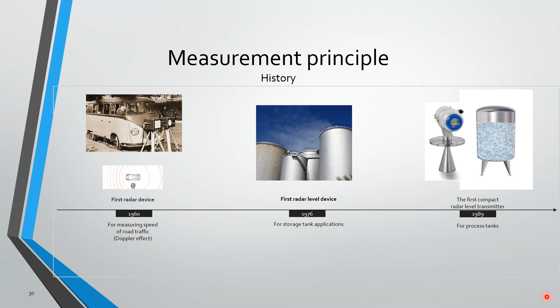1989, the first compact radar level transmitters, and you know, what we have now. The ones we have now are probably a little bit smaller, but these were the first compact units, for process tanks. They were still pretty expensive then, but they've come way down in price since. So again, dielectric constant still comes into play, just like it did with guided wave radar. It's also very, very important with non-contact radar because the dielectric constant of the medium that we're measuring is going to determine how much reflectivity we get from the surface of the material. The amplitude of the reflection isn't quite as important, but we need to get a solid reflection in order to be able to determine the level.